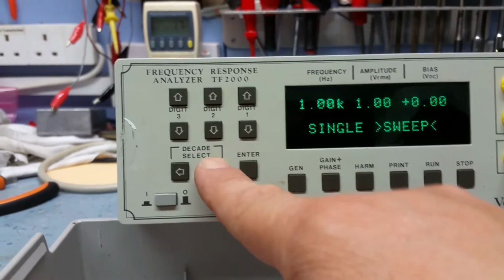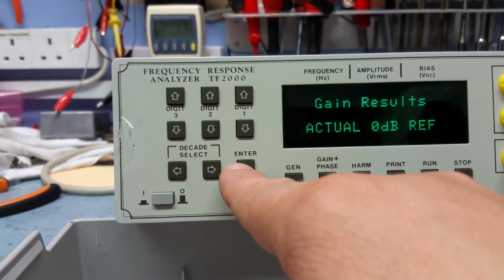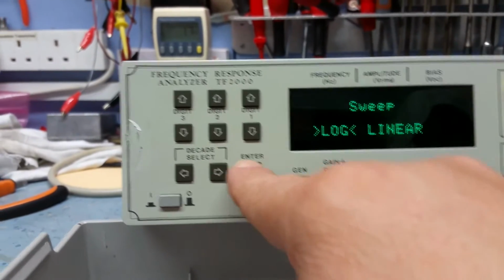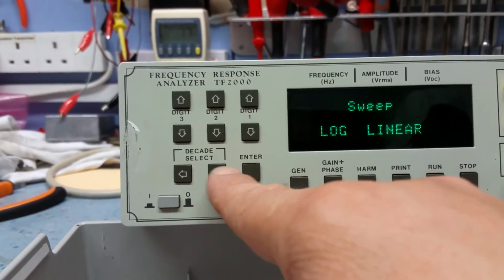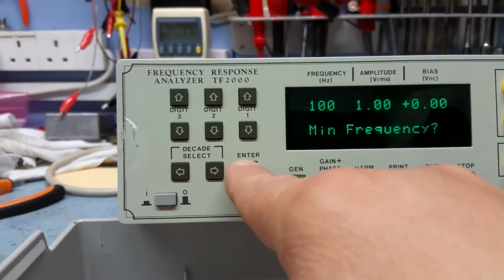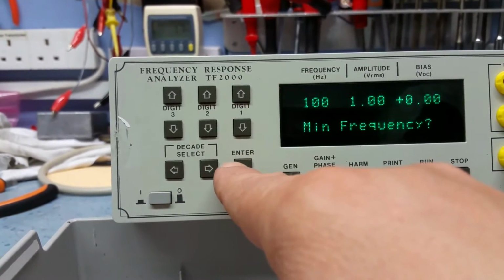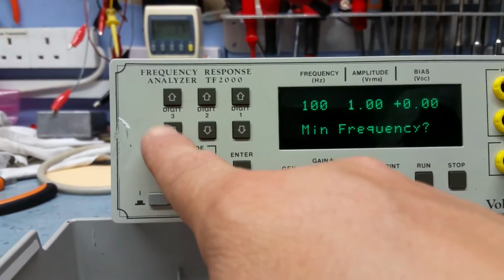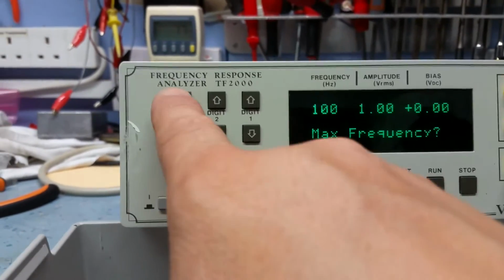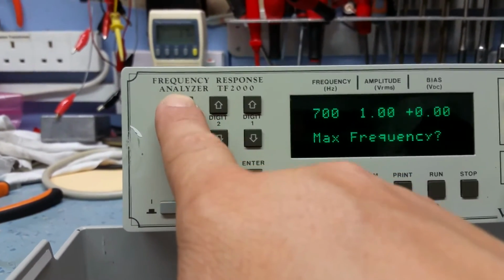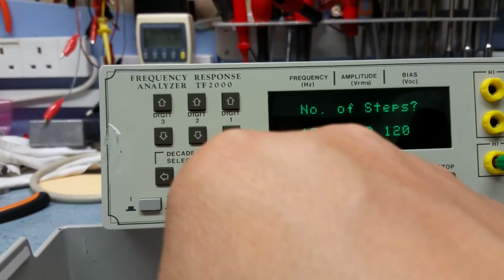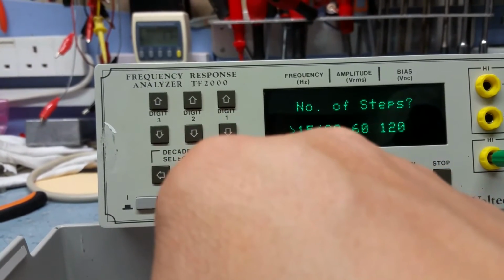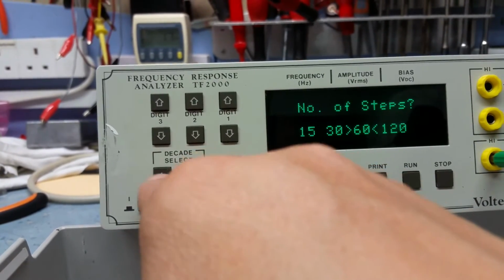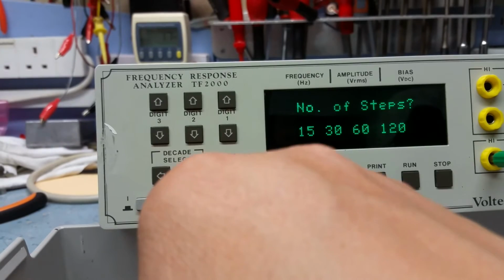Oh, here we go. Sweep. Gain results. Enter. Sweep auto. Sweep linear. Sweep up. Minimum frequency. I don't know what I'm doing here. 100 Hz. Maximum frequency. Let's go 1 kHz. Enter. Number of steps. 15. Oh, okay. We'll have as many steps as possible. Is that as far as we go? Well, I can't get to 120. Okay, 60 then. Ready to sweep. Enter.